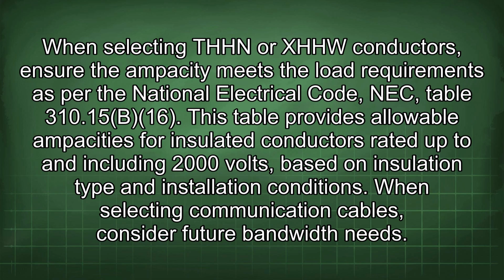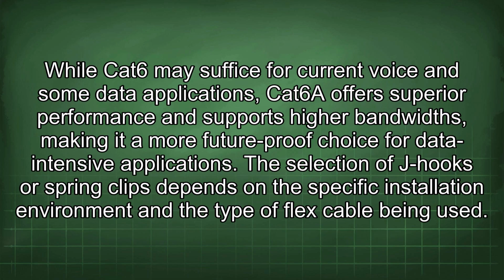When selecting THHN or XHHW conductors, ensure the ampacity meets the load requirements as per the National Electrical Code, NEC, Table 310.15(B)(16). This table provides allowable ampacities for insulated conductors rated up to and including 2000 volts, based on insulation type and installation conditions. When selecting communication cables, consider future bandwidth needs. While Cat6 may suffice for current voice and some data applications, Cat6A offers superior performance and supports higher bandwidths, making it a more future-proof choice for data-intensive applications.